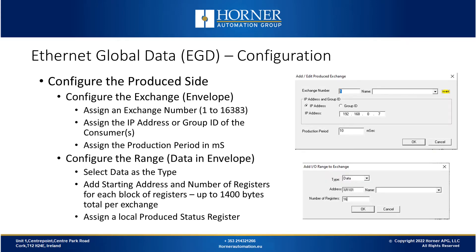Now let's look at configuration and how we set EGD up. First we typically configure the produce side that's sending the data. You configure the exchange for that produce data and assign an exchange number between 1 and about 16,000. Most applications just have a few exchanges. Then we need to assign who we're sending that exchange to. If we're sending it to a single device we'll assign an IP address. If we're sending it to a group of devices we'll assign a group ID, which is a number between 1 and 32. Then we have to assign how often we'll produce or send the data in milliseconds.